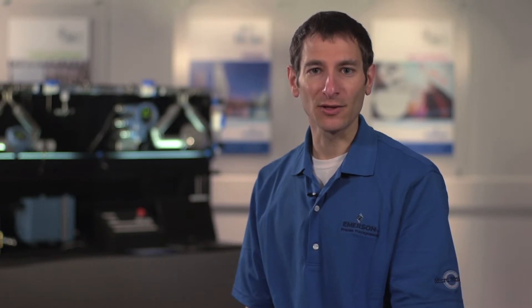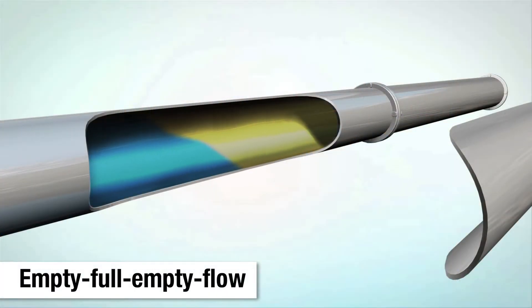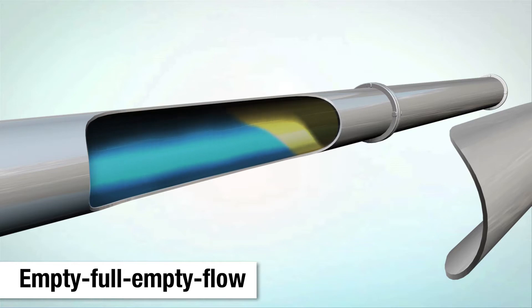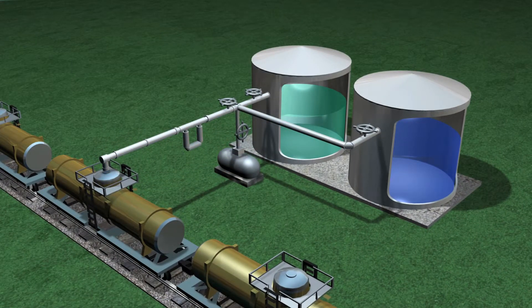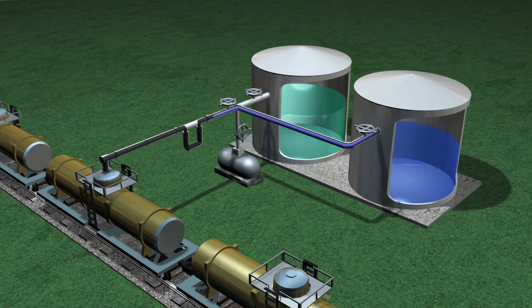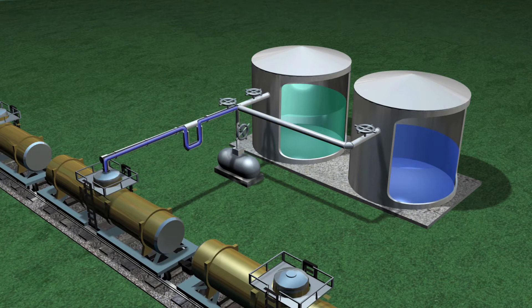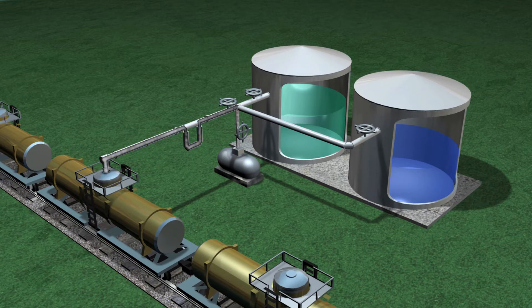Empty-full-empty flow applications include truck and tank loading and are characterized by a precise liquid-to-gas interface. This railcar loading process illustrates two products metered through one meter at different times. To avoid cross-contamination, the meter is blown dry between batches. Each batch begins empty, fills, then ends empty.